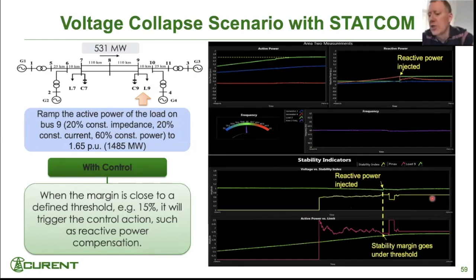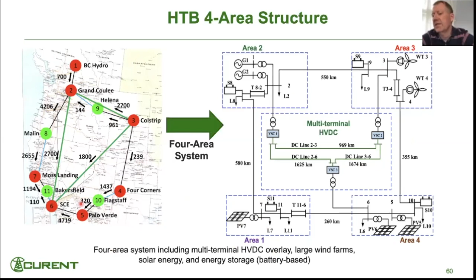We developed a structure to also represent the western part of the United States. We call it our 4-area system, but with high penetration levels of PV and wind. So it's based on the grid of today, but we replace some of our sources that are currently coal and natural gas with PV and wind, and look at how we can control things. The grid is easy to do when everything's running fine, but it doesn't work well when you lose a large transmission line or large generator.